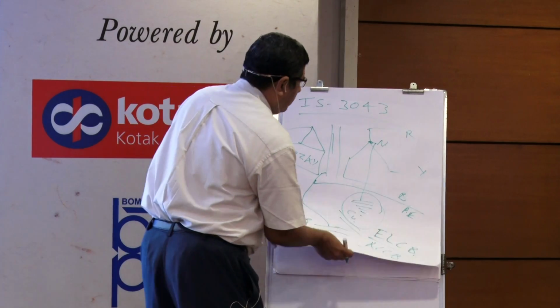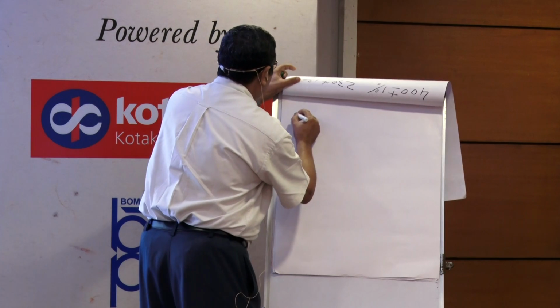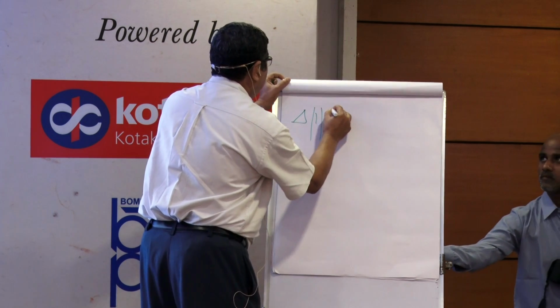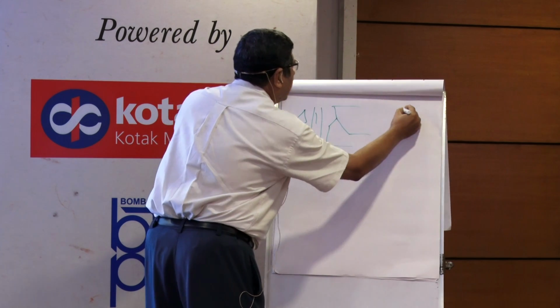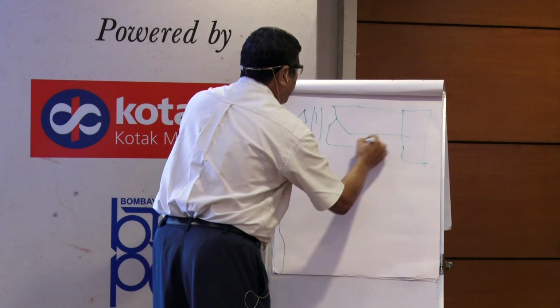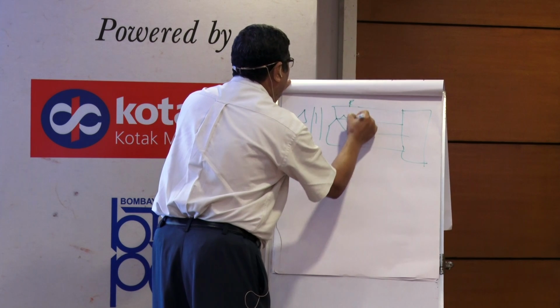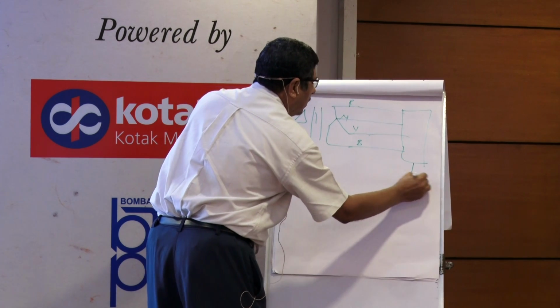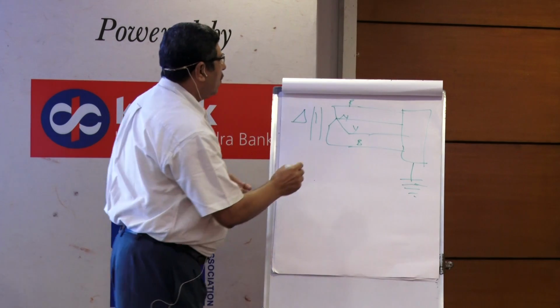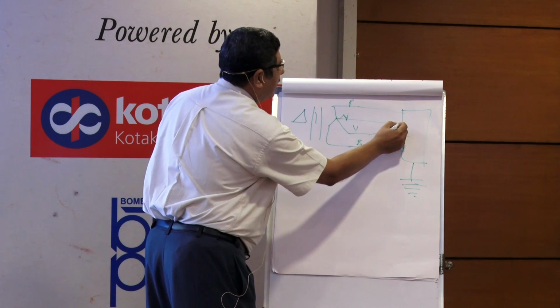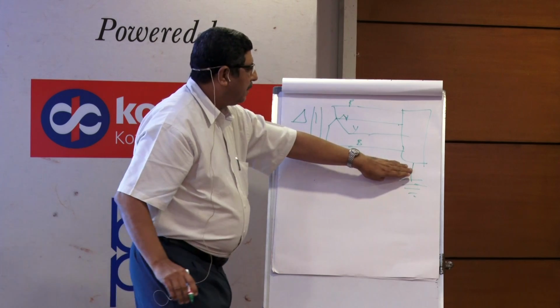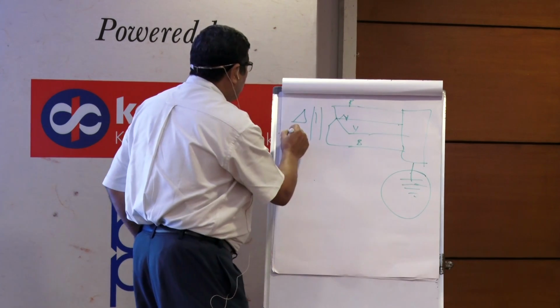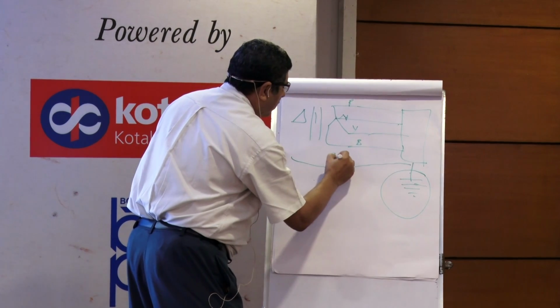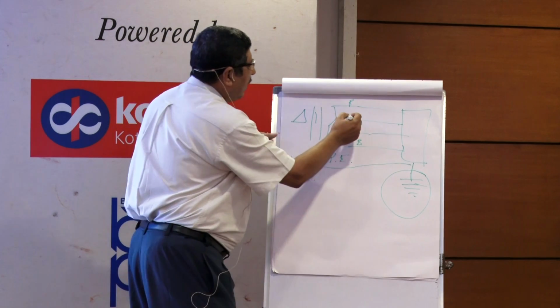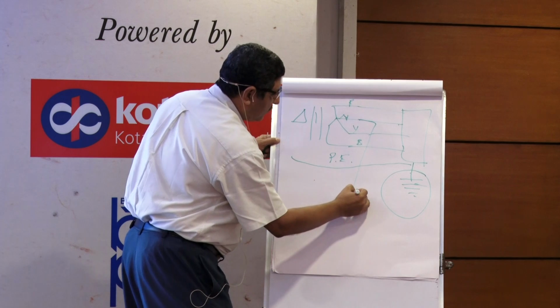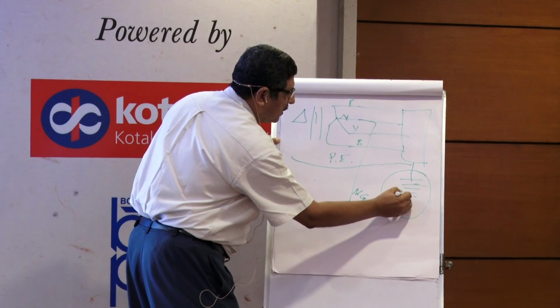Let's say this is your machine, and this is your body earth. Many people take a shortcut - they take this point and this point as common. Normally, this point is done separately at our factory end, because no supplier gives you protective earthing potential separately. This is also created if you have your own transformer at your end. This is earth. So this is what we call neutral grounding, and this is what we call protective earth or earthing.